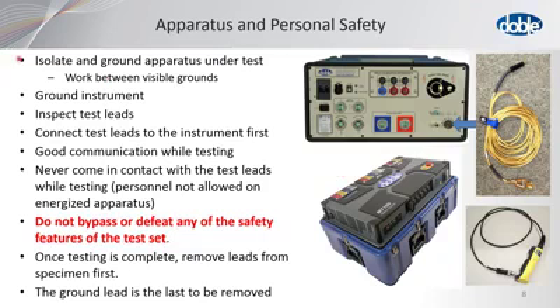We want to make sure to first isolate and ground the apparatus under test. And so you want to make sure that, of course, the connections to that apparatus are grounded before you remove them, and to work between visible grounds. That promotes a safe environment for testing. You want to make sure the instrument is grounded.